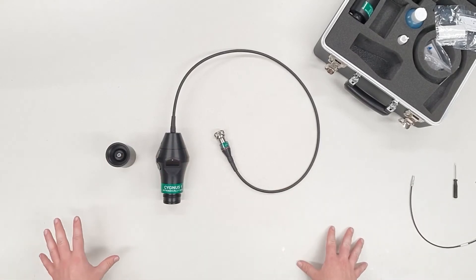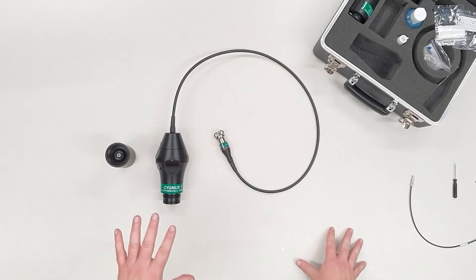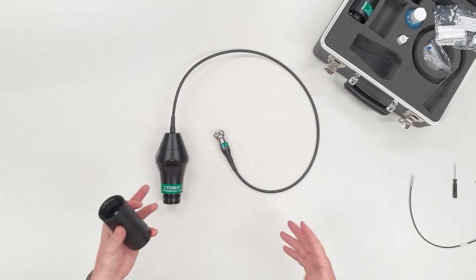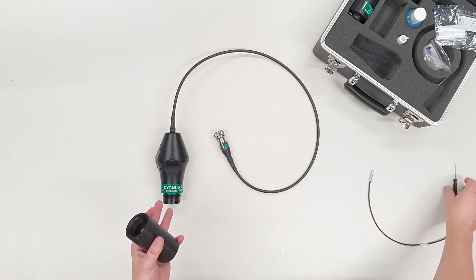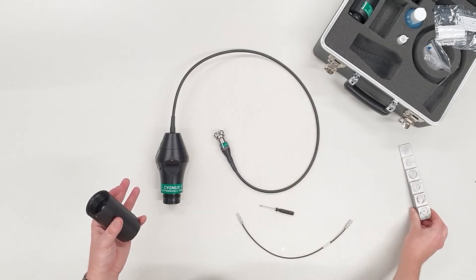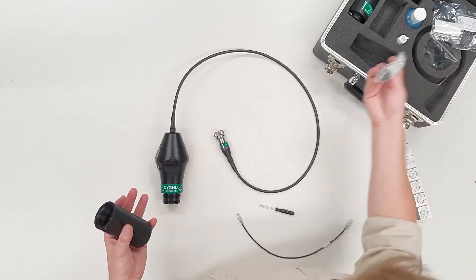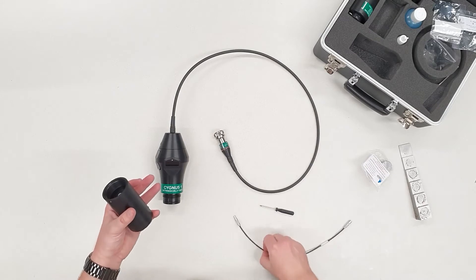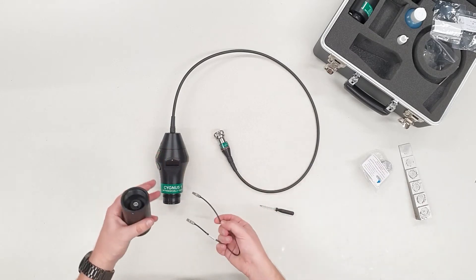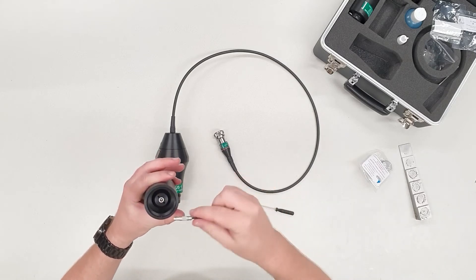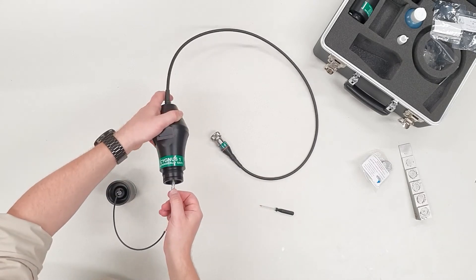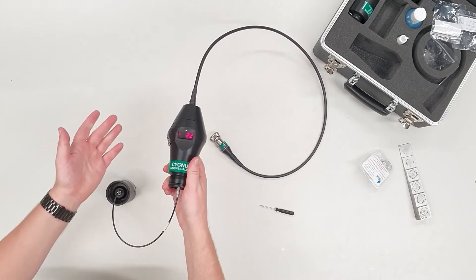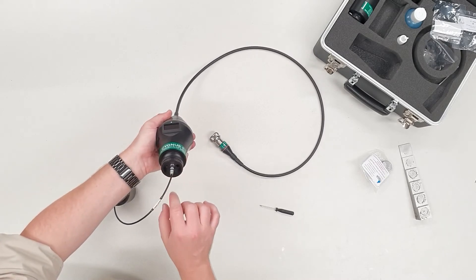The calibration of these units is fairly simple. You'll want to do this before you go to site. This has to be done in a safe place, as it requires removing the battery from the unit, which is not intrinsically safe. You really only need three things: your test block, which is a 15 mm test block, and your jumper cable, which is just a cable for connecting the battery without actually having to screw it in place. It allows you to power on the unit without screwing the battery in, giving you access to the controls hidden underneath.